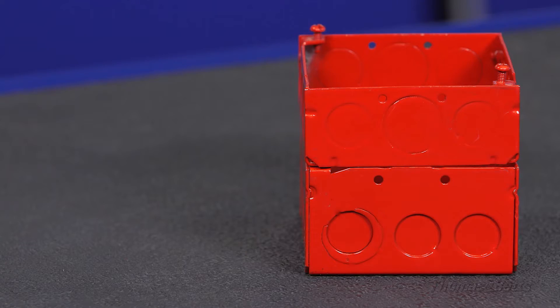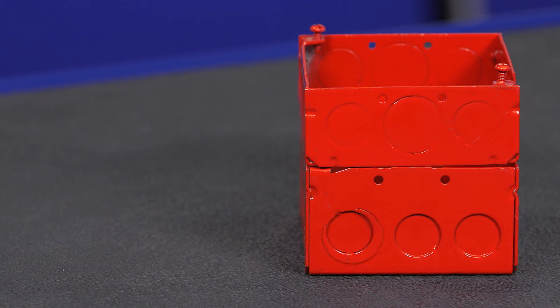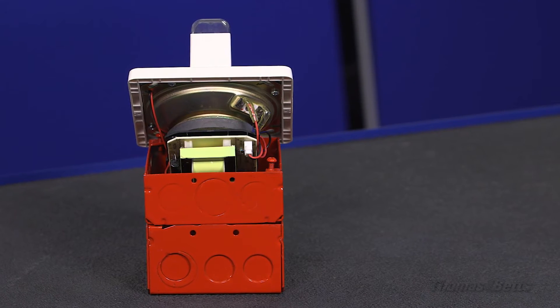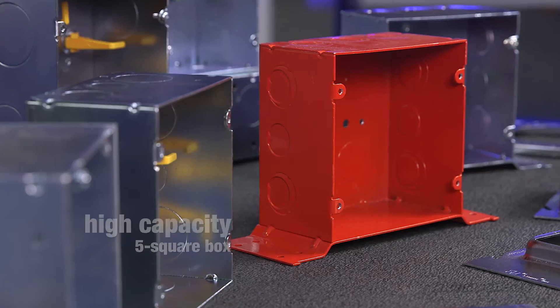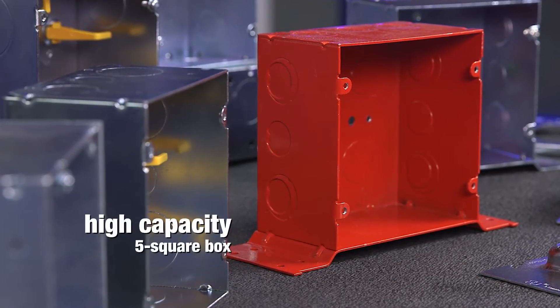For fire alarm applications, a box extension is typically required to enable a standard four square box to accept a large fire alarm device. Even with a box extension, conductors are crowded around the device, leading to frequent ground faults and short circuits. Using the higher capacity five square box can dramatically reduce the troubleshooting time associated with these issues.